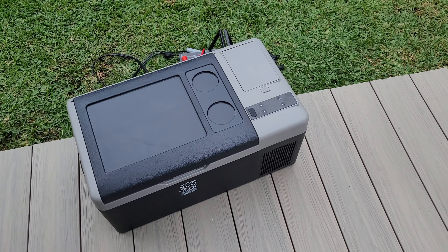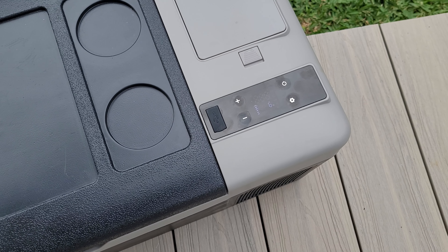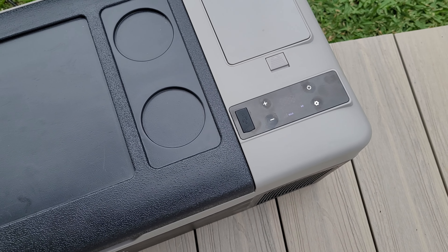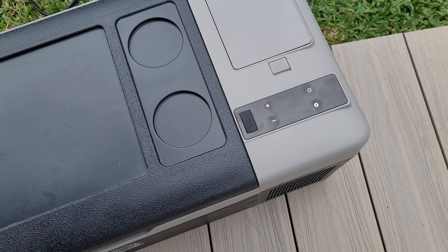It's just been an hour and it's sitting on two degrees. I'm not going to wait any longer, but I would say it takes about an hour to an hour and fifteen minutes to go under zero degrees, down to around minus four.